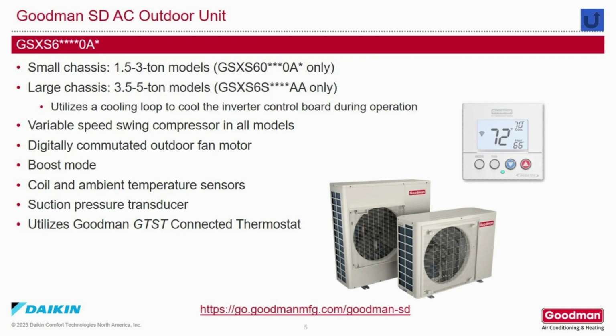The Goodman Side Discharge Cooling Only Outdoor Unit. There are two chassis sizes for the Side Discharge Cooling Only Outdoor Unit. Small chassis, 1.5 to 3 tons. Large chassis, 3.5 to 5 tons. The large chassis utilizes a cooling loop to cool the inverter board during operation. The small chassis uses aluminum cooling fins coming off at the back of the board into the airflow to cool the inverter during operation. Variable speed swing compressor on all models.